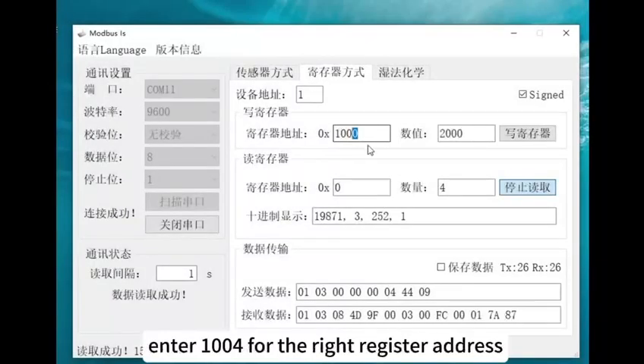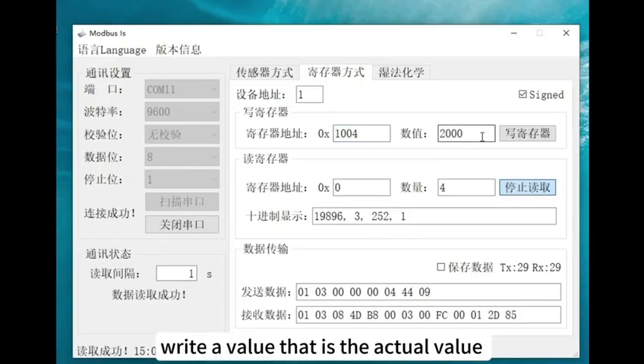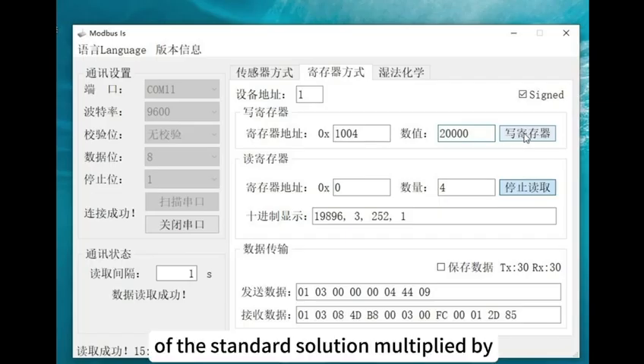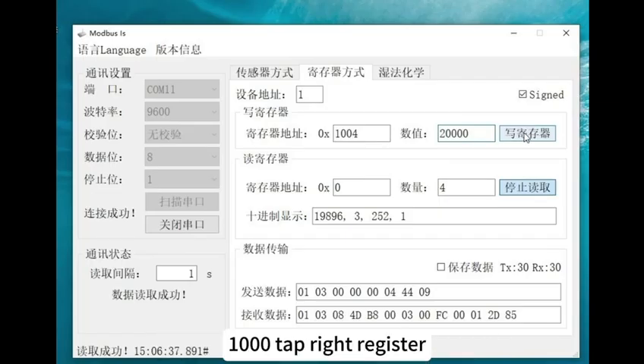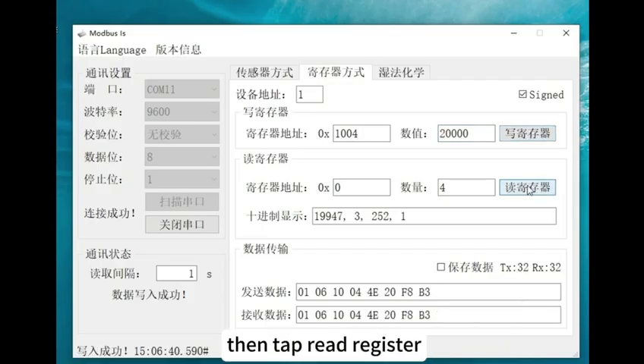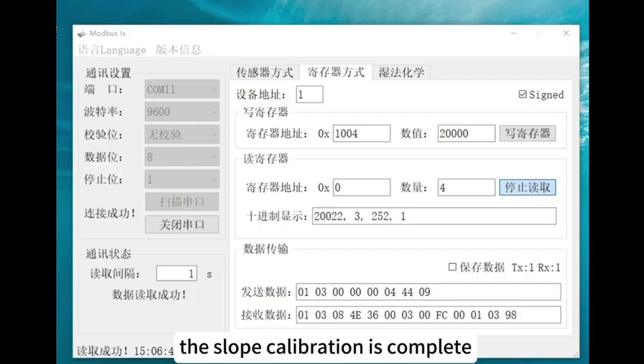Enter 1004 for the write register address. Write a value that is the actual value of the standard solution multiplied by 1000. Tap Write Register, then tap Read Register. The slope calibration is complete.